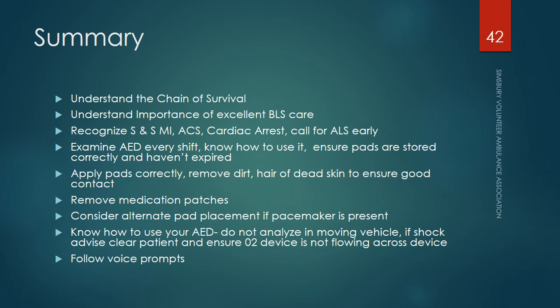Prior to placing the pads, you're going to make sure that you put them in the right spot. You're going to clear any dirt, hair, dead skin, anything that's going to prevent a good contact with the patient. You're going to ensure that the chest area is clean. Put them in the right place and make sure that it has good contact with the skin, taking into consideration patients that are obese and patients that are extremely thin. They both provide challenges when it comes to ensuring that the pad itself has 100% skin contact. Remove the medication patches from the chest area.